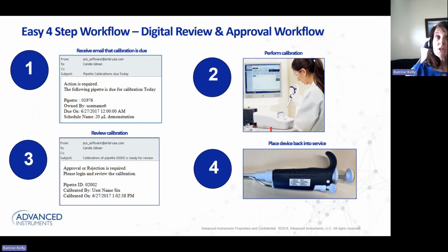The software allows for a digital review and workflow. The digital review and approval workflow means that the pipette owner will receive an email notification that a pipette is due for calibration. They then perform a calibration in the lab, and an email is sent to the reviewer that it's ready for review. The reviewer can then log into the software from their office and review and approve the calibrations remotely. Once the review is complete, the calibration label can then be printed. If the email notification is not set up for whatever reason, the reviewer can log into the software in the lab when the calibrations are ready to be reviewed, and those calibrations will be highlighted on the home screen for them.